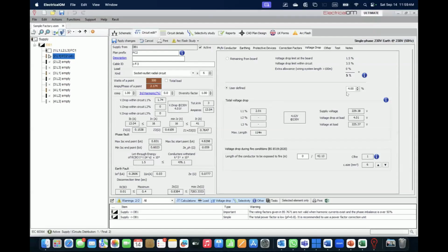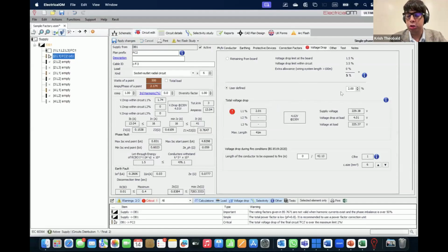Number two, I can say I want only 2% voltage drop in this circuit. Now, if I put 2% voltage drop, you see it will flag a warning because it's actually 2.01 here. So I can set either the remaining from the board or a predefined value. For example, if I say remaining from the board, 1.5, 3. Because it's a socket circuit, we are allowed 5%.